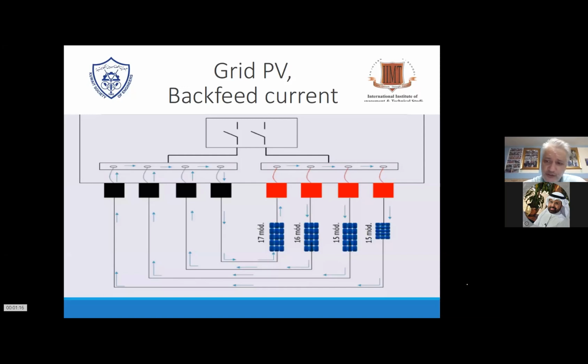So it could work during daytime, when the sun hits 5 hours, 6 hours, because then the voltage is usually getting to 500 volt with the old system. With a 1000 volt system, it's mostly 600 to 700 volt. So depending on how many diodes are defective or how many modules are soiled or temporarily out of operation or optimal operation, they will get hurt all the time. So that could happen daily or monthly or weekly, but it's a problem.